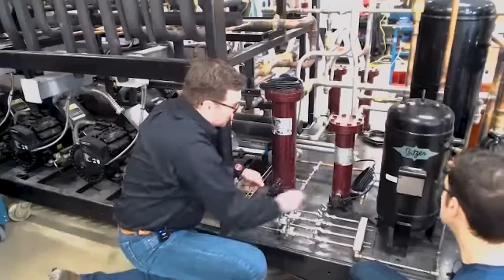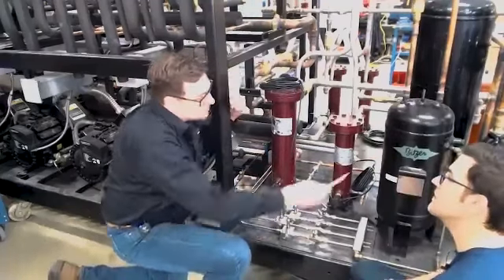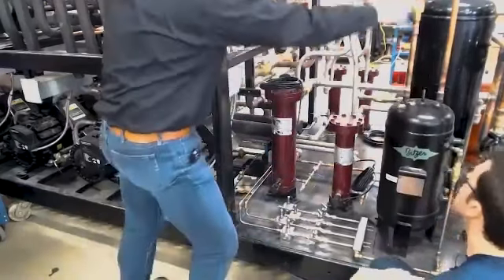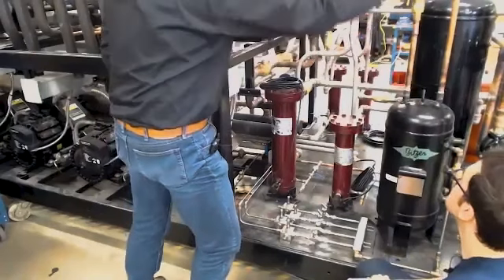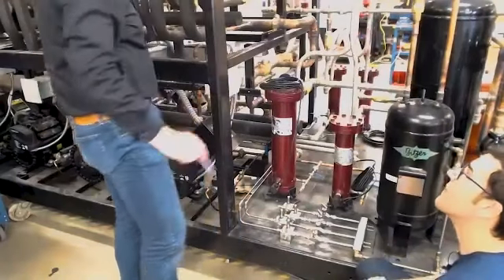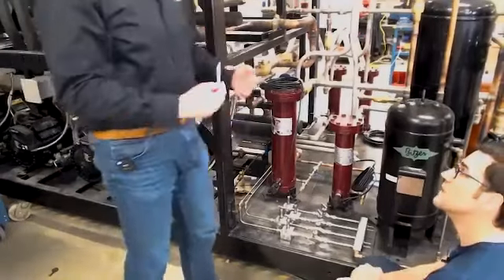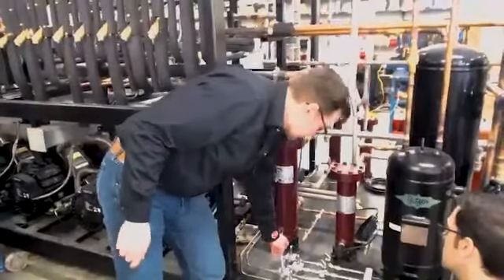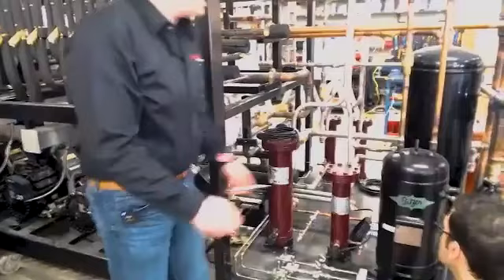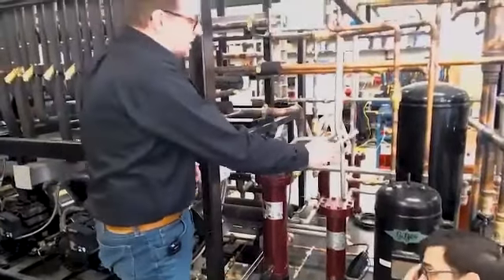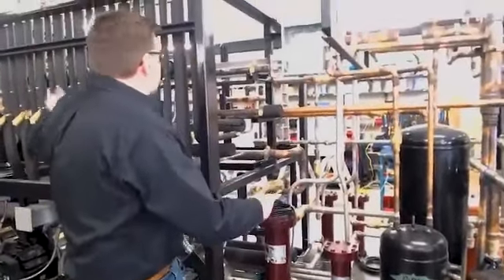Now it's important - how do we keep this flowing? We depressurize the oil reservoir into the flash tank. So it is a constant depressurization. When this block solenoid opens, we have a good pressure differential between the oil reservoir and flash tank that we feed.